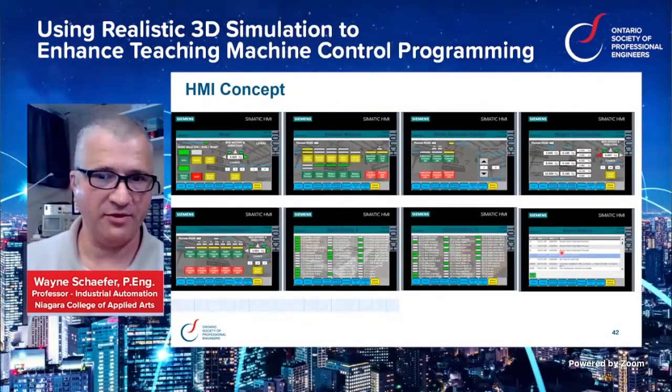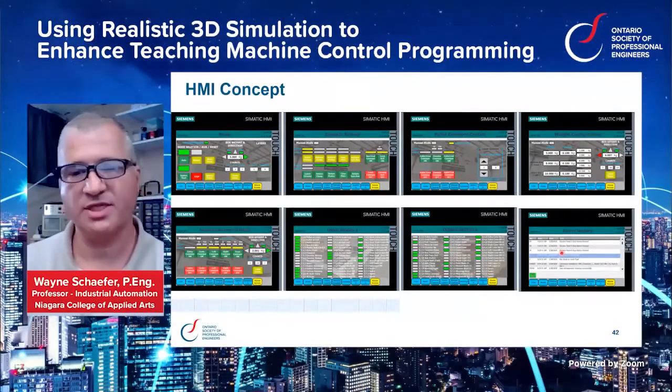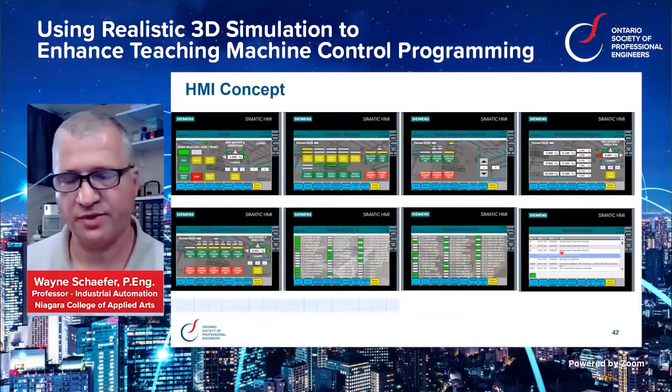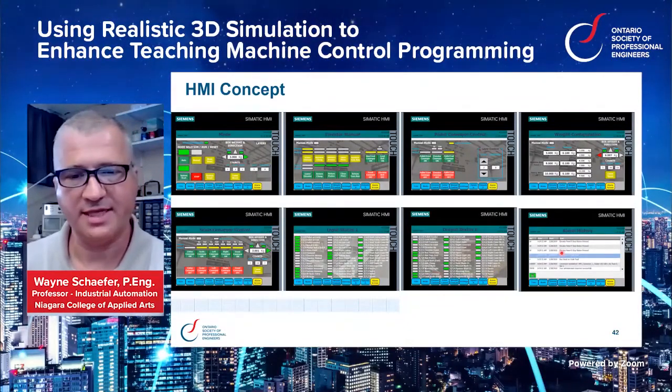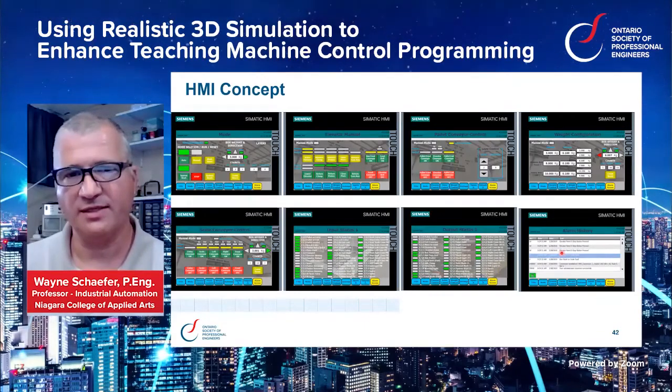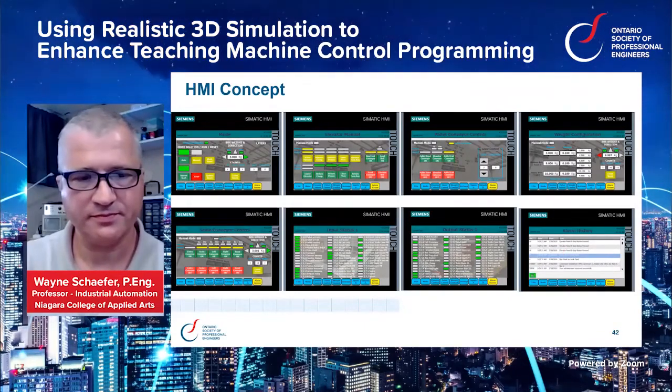So why is this a flat menu concept? Because all screens are accessible from each other. There's no searching for a screen. There's minimal operator training required. There's still password required to get into the settings screen, but that doesn't violate the flat menu concept.